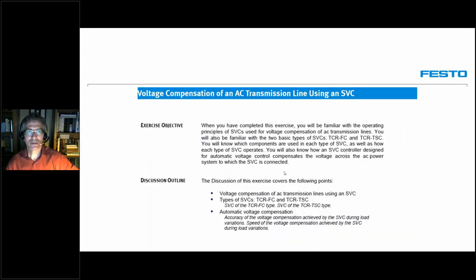So this is what we just saw. Now we attack the second part of the presentation about voltage compensation of an AC transmission line using an SVC, or static VAR compensator. The discussion will go through voltage compensation using an SVC, the different types of SVCs, the TCR FC and TCR TSC, and then we will have the hands-on part where we look at the automatic voltage compensation.